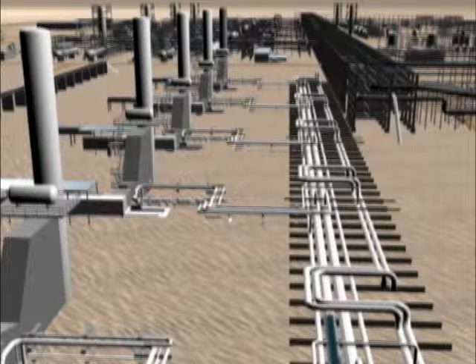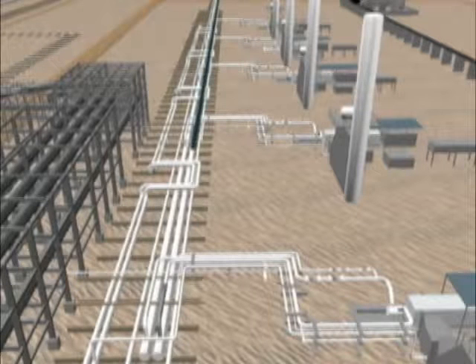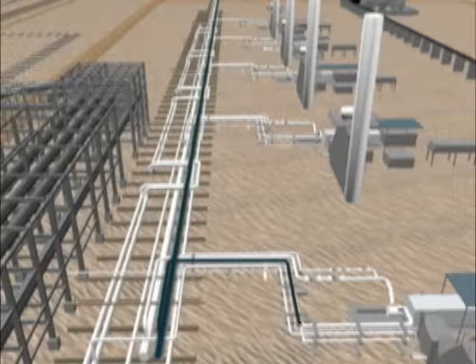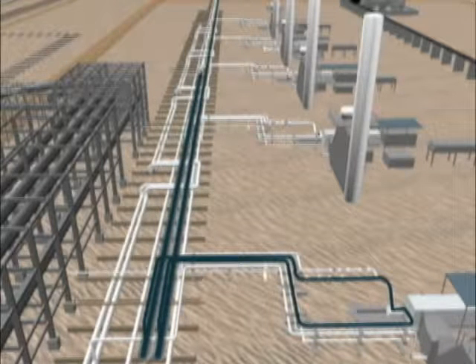Water injection plant will house a 13.8 kV substation, process interface building, instrument air system, fire water system, and team building and water injection facility. To achieve 2,850 PSIG for the 2.14 million barrels per day of treated seawater coming from the Andar water injection plant, the Khurais water injection plant will utilize five turbine-driven injection pumps, each delivering a total of 12,500 gallons per minute to both Khurais and Abu Jufan fields.